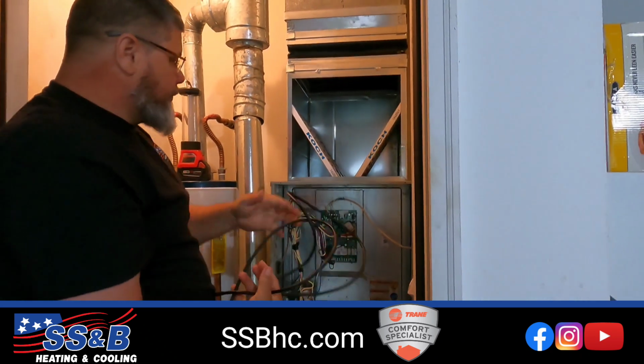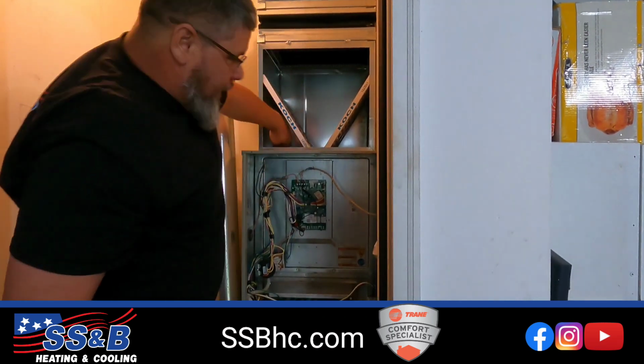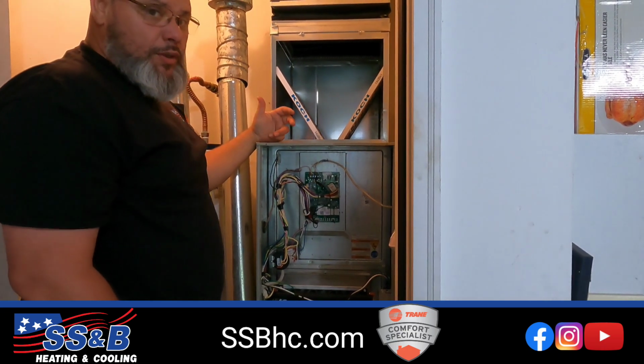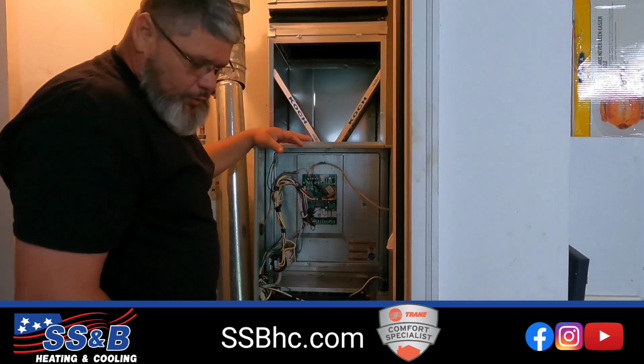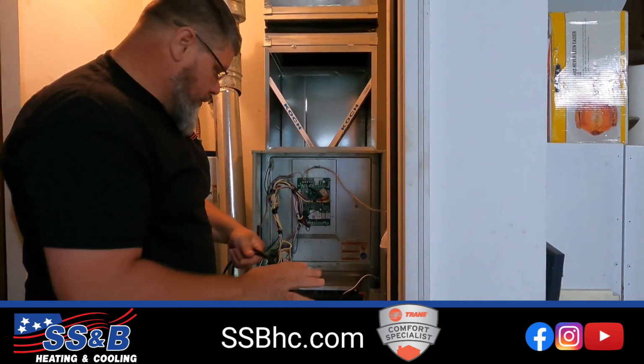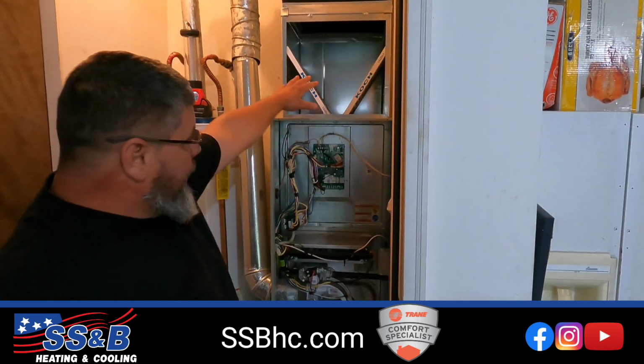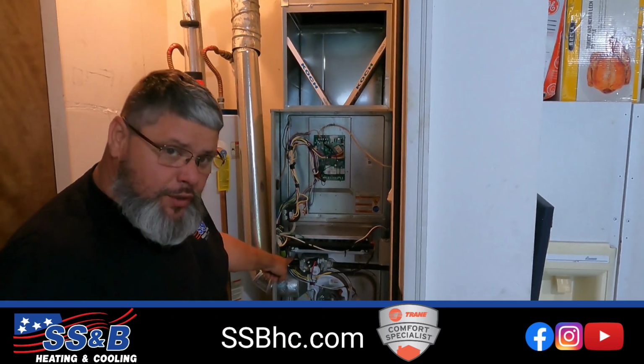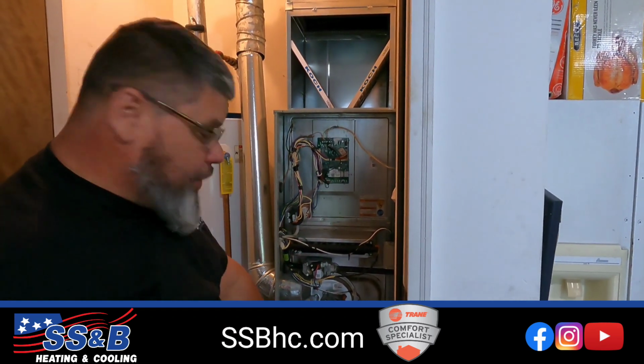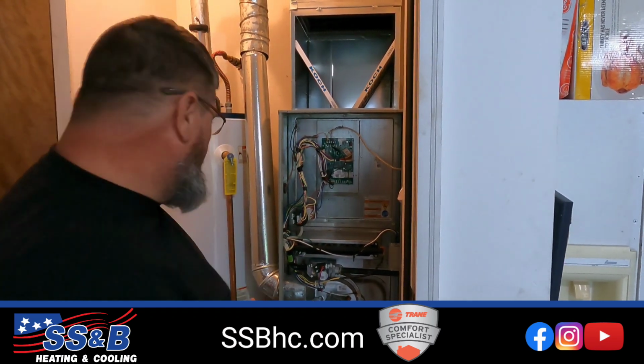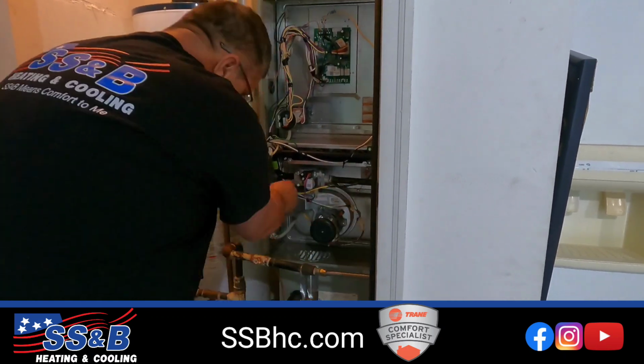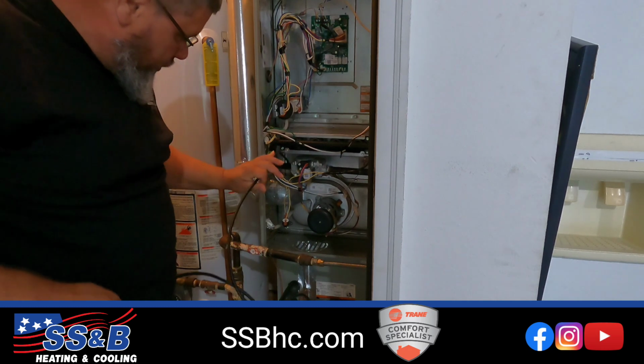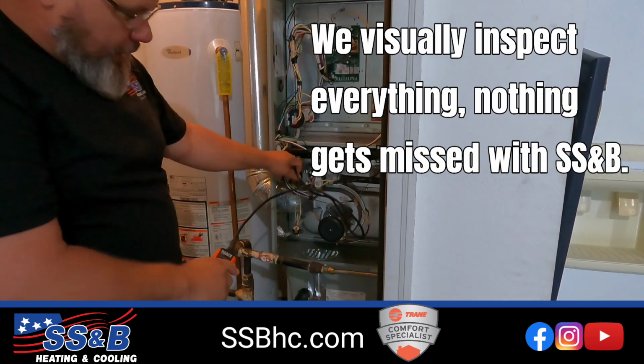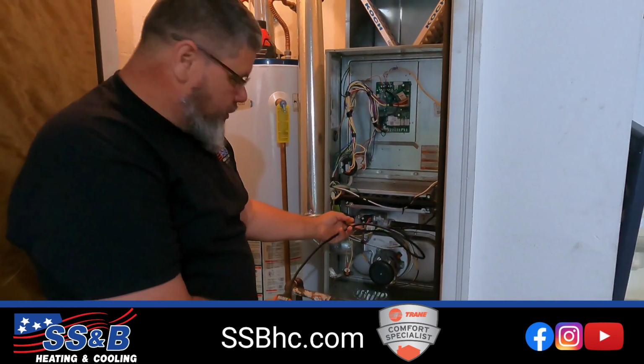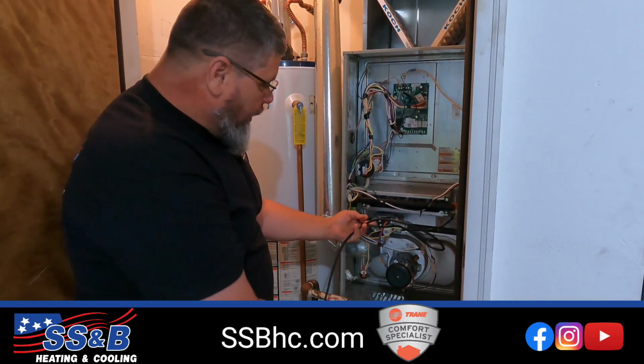There's also a capacitor that is down inside this blower that we actually pull so that we can check, make sure that it's within spec as well. This one is an actual ECM motor, so there is not a capacitor on this one. Once we get that up here checked, then we can actually remove the limit switch, at which time we can actually go down through the furnace and check the evaporator coil without having to tear all that panel apart. And then we can actually go all the way down from here into the evaporator coil at the bottom down here. And that allows us to see and evaluate and make sure that any dirt might be bypassing filters and might need additional cleaning as well.